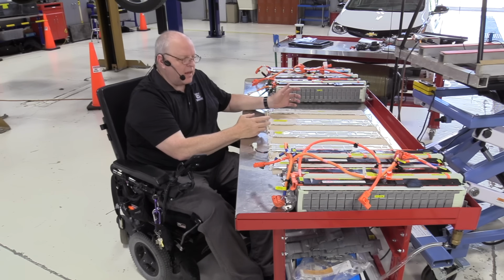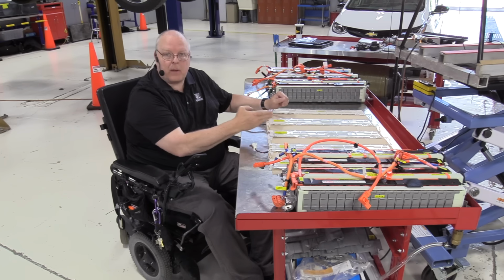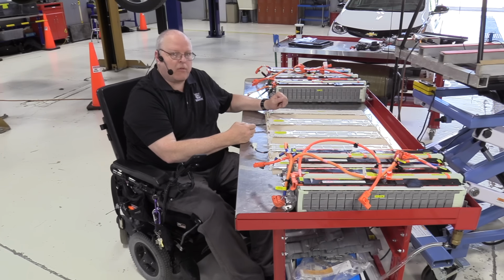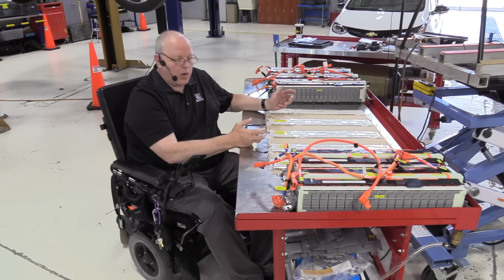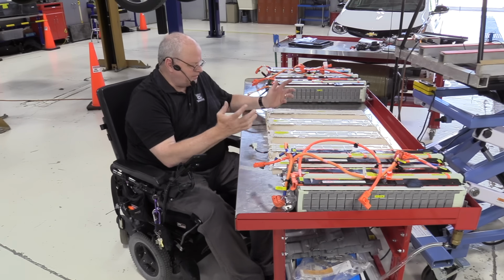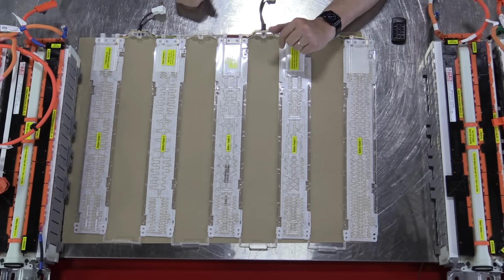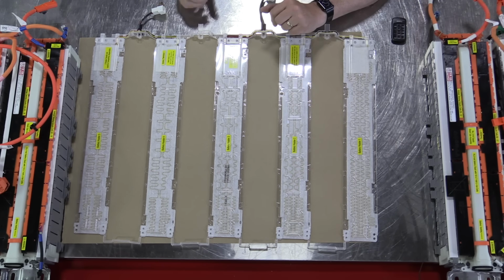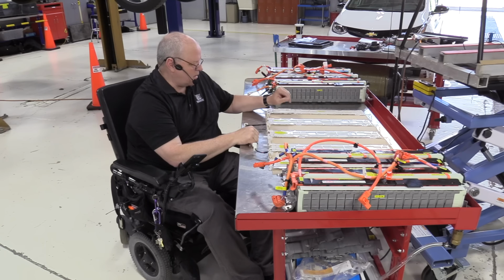If we command both heaters on, but we see from the temperature sensor that only one of them is working, then we can set a trouble code for a heater circuit problem. That's the purpose of the 2 thermistors here, to diagnose whether or not the heater circuit is working as it should.